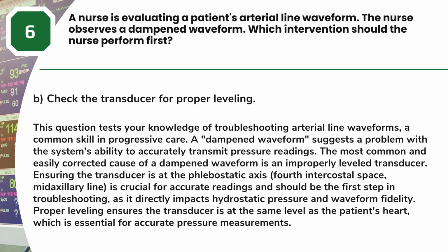This question tests your knowledge of troubleshooting arterial line waveforms, a common skill in progressive care. A dampened waveform suggests a problem with the system's ability to accurately transmit pressure readings. The most common and easily corrected cause of a dampened waveform is an improperly leveled transducer. Ensuring the transducer is at the phlebostatic axis, fourth intercostal space, midaxillary line, is crucial for accurate readings and should be the first step in troubleshooting, as it directly impacts hydrostatic pressure and waveform fidelity. Proper leveling ensures the transducer is at the same level as the patient's heart, which is essential for accurate pressure measurements.